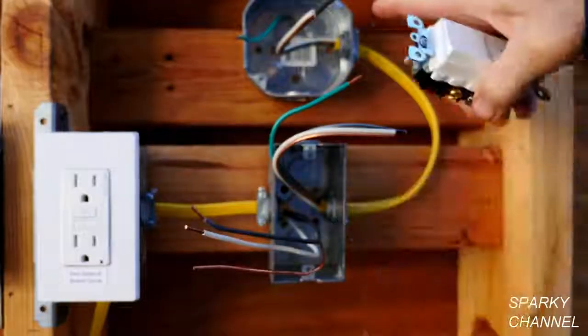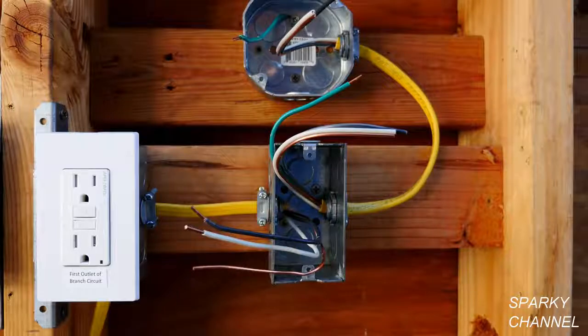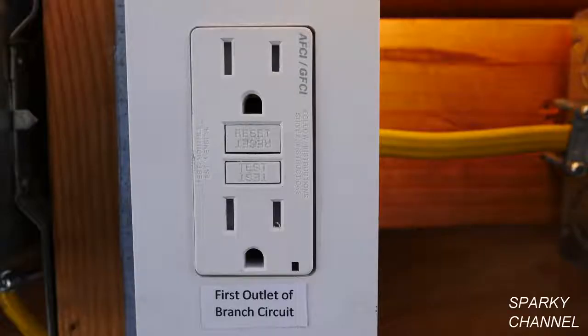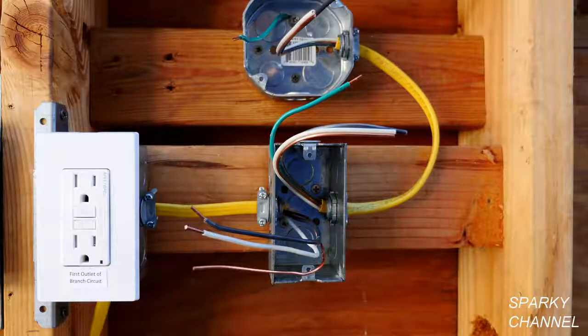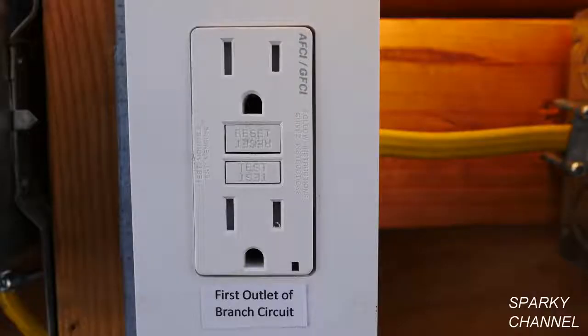This circuit represents a kitchen circuit, and kitchen circuits now require both arc fault circuit interrupter protection and ground fault circuit interrupter protection. These codes can be found in NEC code 210.8 for the ground fault circuit interruption and 210.12 for the AFCI protection. Also, I have a video on this particular device, the AFCI GFCI device, and it goes over the code very carefully.